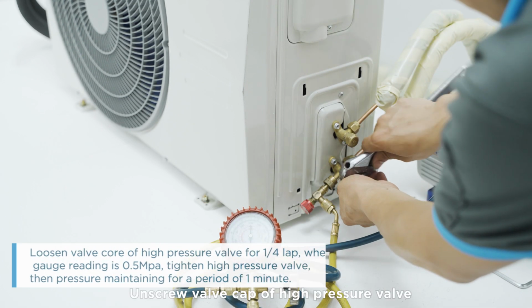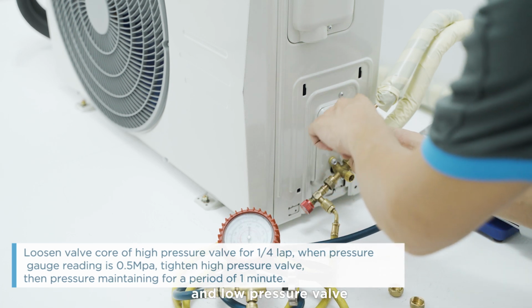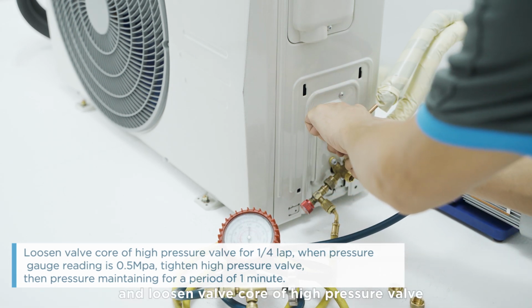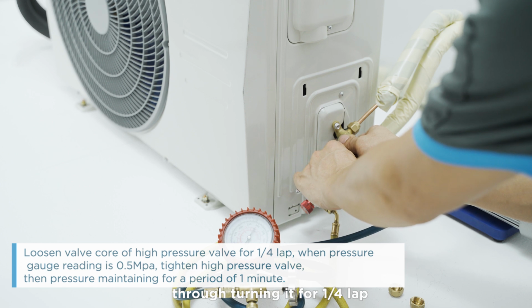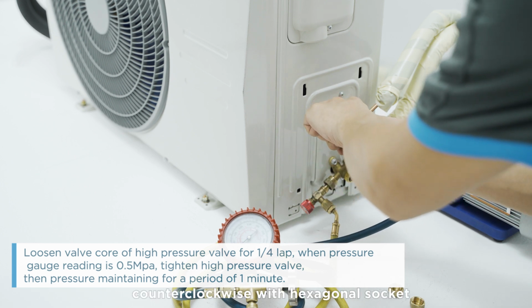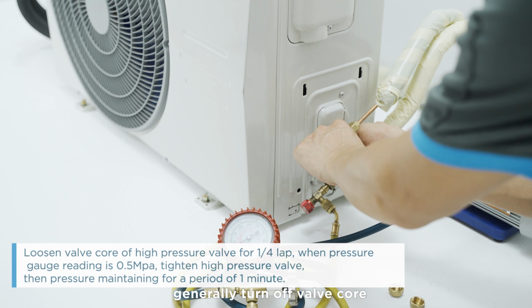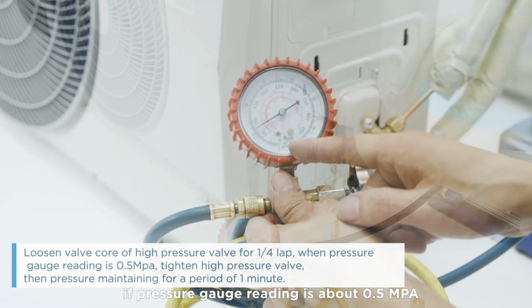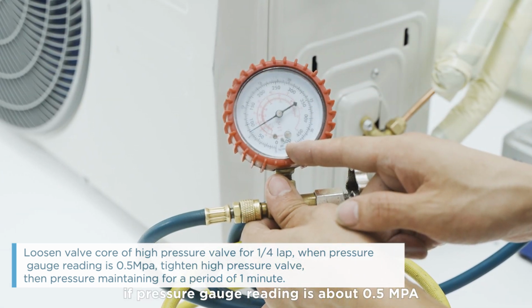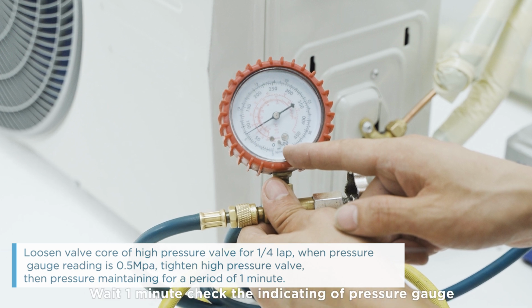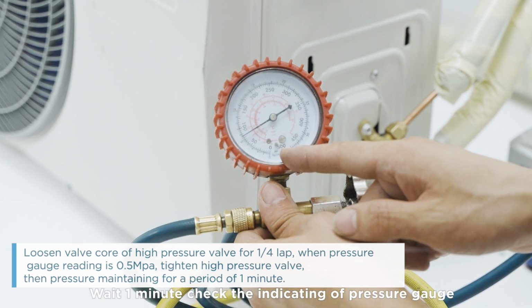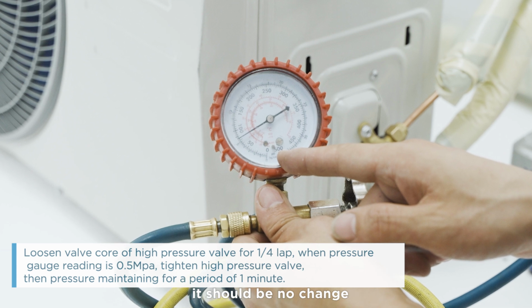Unscrew the valve caps of the high pressure valve and low pressure valve, and loosen the valve core of the high pressure valve by turning it 1/4 lap counterclockwise with a hexagonal socket for 5 seconds. Generally, turn off the valve core if the pressure gauge reading is about 0.5 MPa. Wait 1 minute, check the indicating of the pressure gauge. It should be no change.